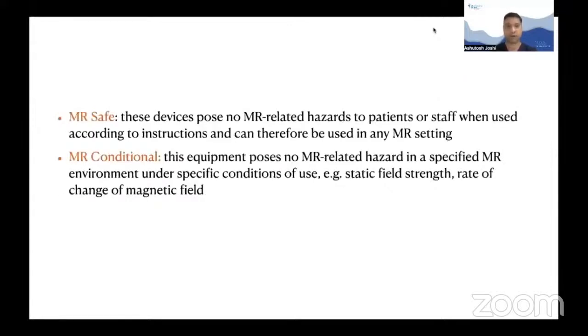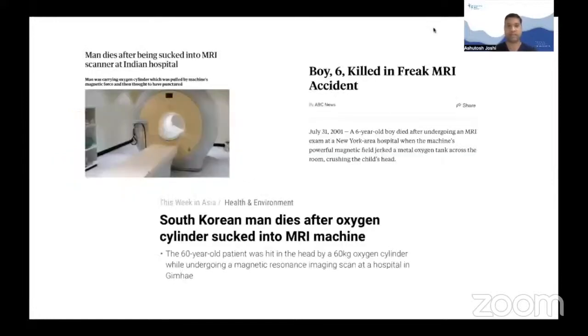All equipment used in the MR suite should either be MR safe or MR conditional. MR safe means that these devices pose no MR related hazards to patients or staff when used according to instructions and can therefore be used in any MR setting. MR conditional means that these equipments pose no MR related hazard in a specified MR environment under specific conditions of use, for example static field strength or rate of change of magnetic field.